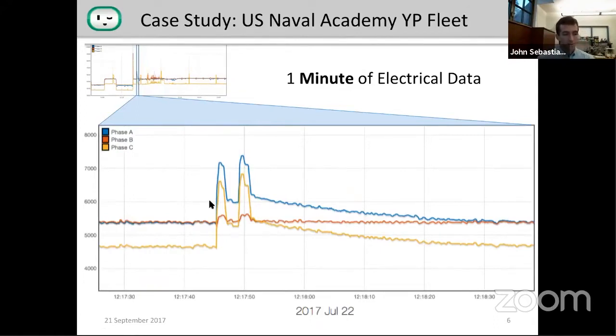That's really where we deliver actionable insights to the crew, by saying, hey, that's the chill water pump, and we expected it to only run at the beginning of a cruise, but yours is running every hour. Maybe that indicates a bearing has gone bad, or that the pressure sensor on the system isn't functioning correctly.